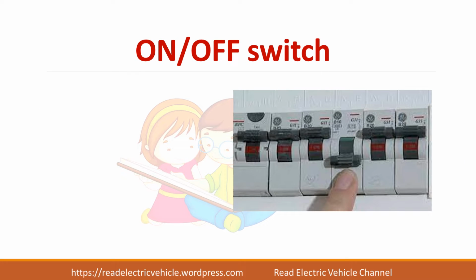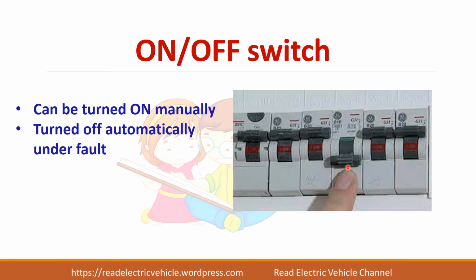Next we will see about the on-off switch in MCB. So we can see here these are all MCBs which are in on position except this one. So all these MCBs can be turned on manually. That is, if you pull up, it will get turned on. Whenever it detects any fault, it will come down automatically, or turned off automatically under fault conditions. After the repair work, you can turn it on manually. So this represents the off position and this one represents the on position.